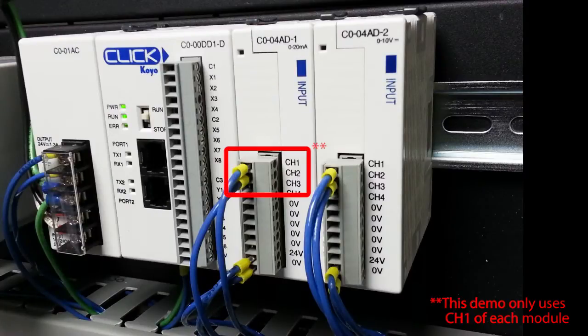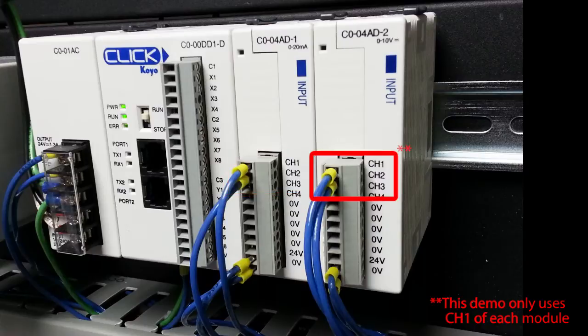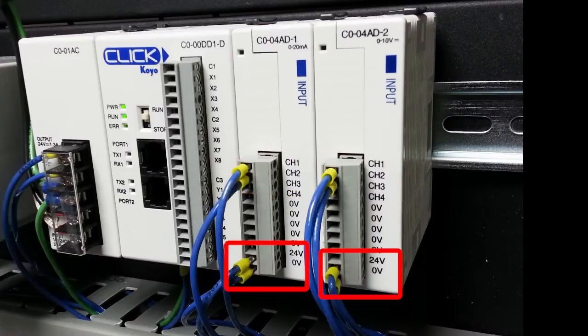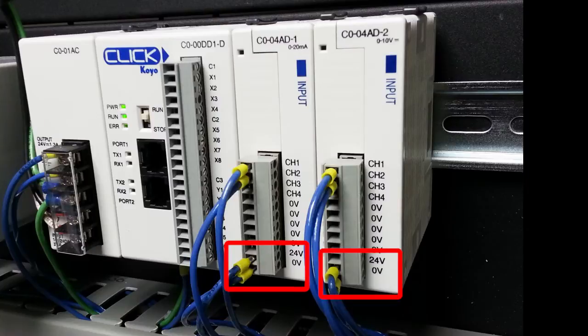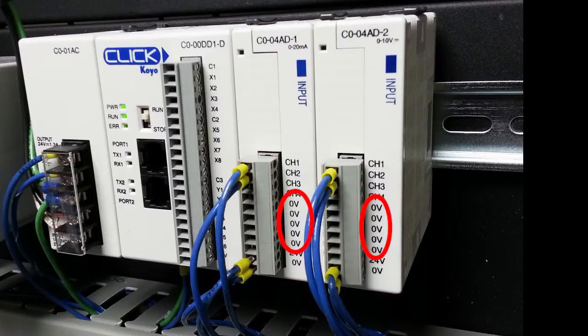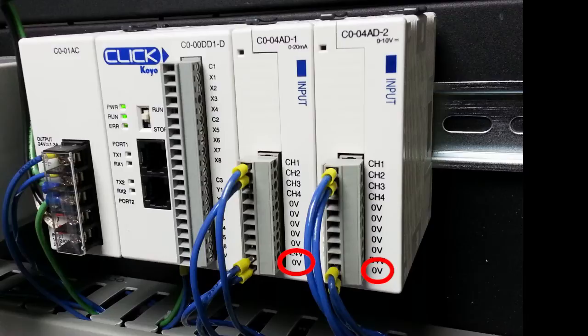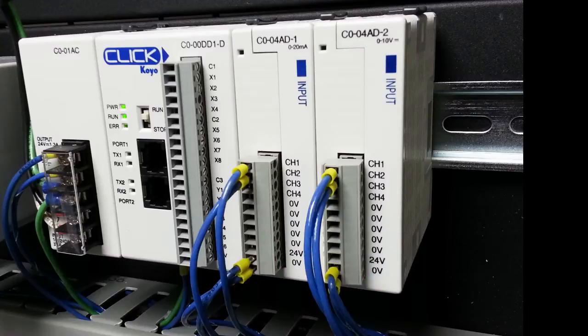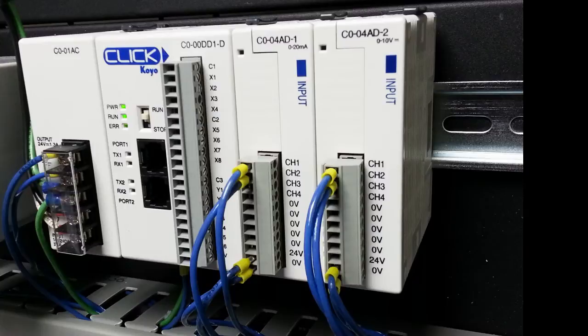We have two of the current inputs wired and two of the voltage inputs wired, even though we are only using one of each. And here is the 24 volts required by both modules. These zero volt points are electrically connected to this zero and are provided for your convenience to tie off the sensor commons. Our test setup has all the sensor commons tied together off screen on some DIN-REL terminal blocks which are electrically connected to these so we are in good shape.